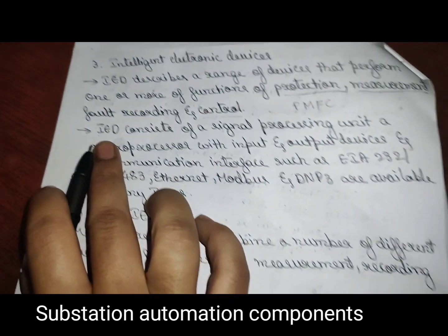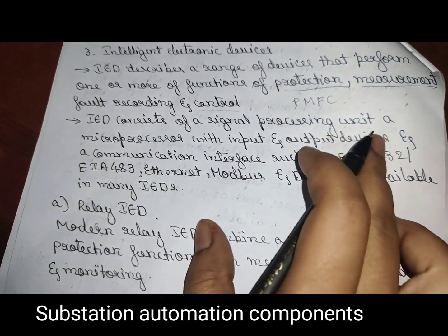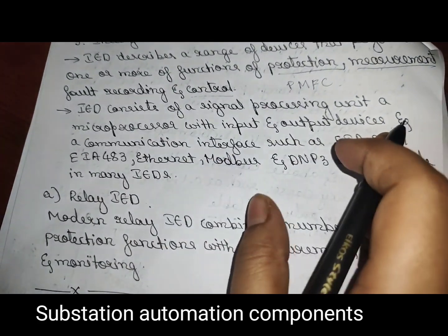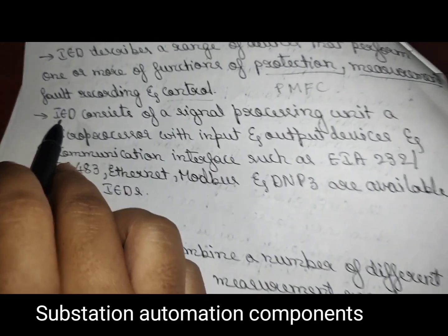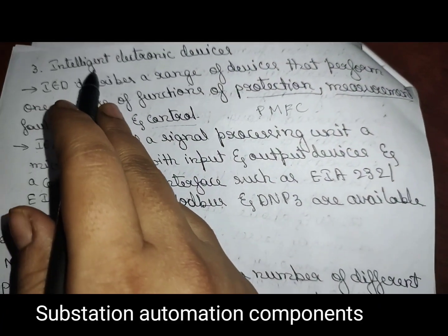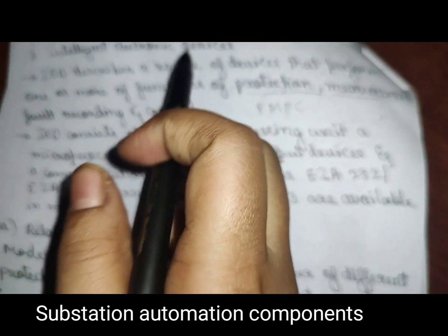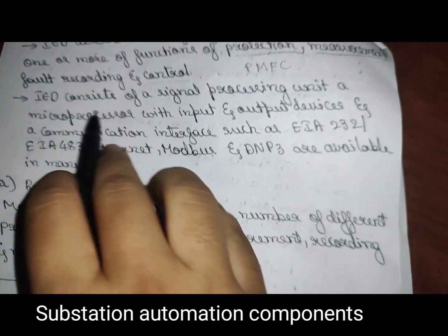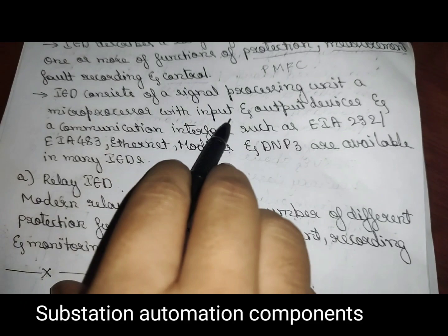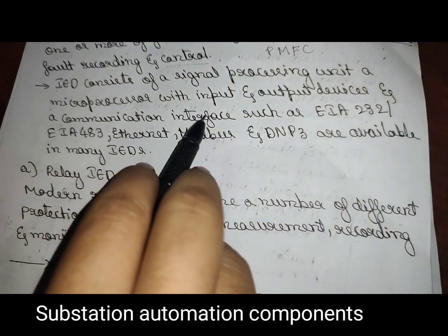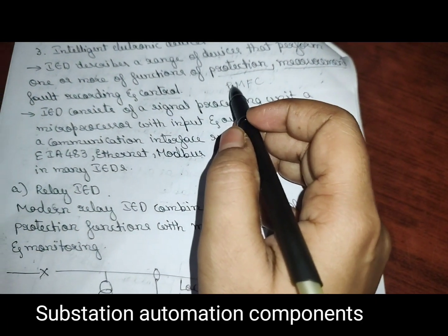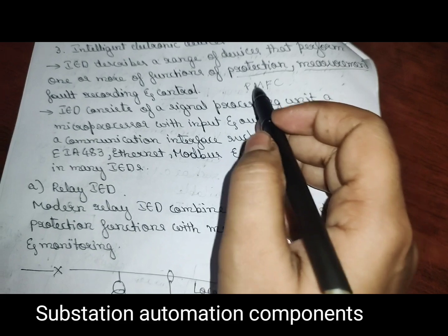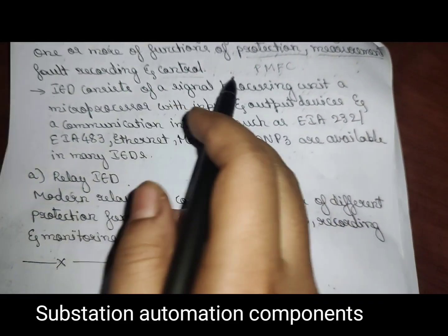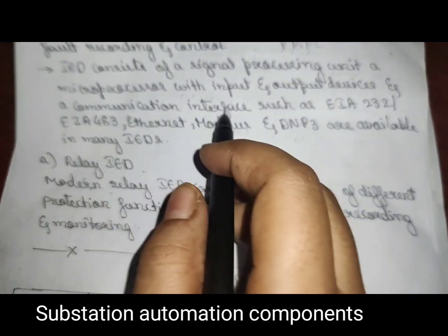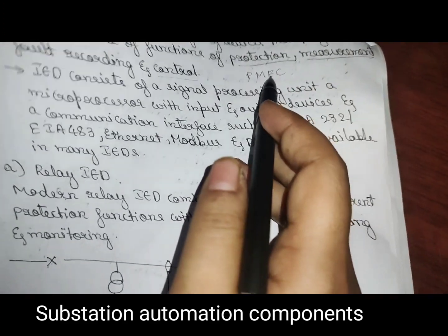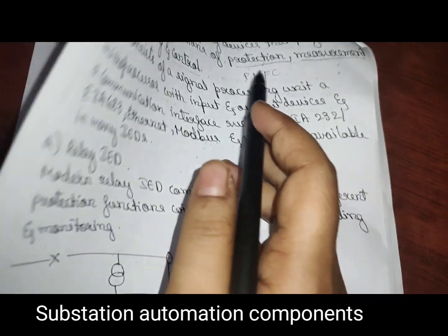So IED consists of a signal processing unit, a microprocessor with input and output devices. So what does IED contain? You can remember intelligent electronic devices. Electronic devices means you will get a signal. It consists of a signal processing unit, a microprocessor with input and output devices, and a communication interface. So in order to protect, measure, record faults and control, we need a signal processing unit and microprocessor, and the communication interface is more important to control, to protect, and for measurement and fault recording also.